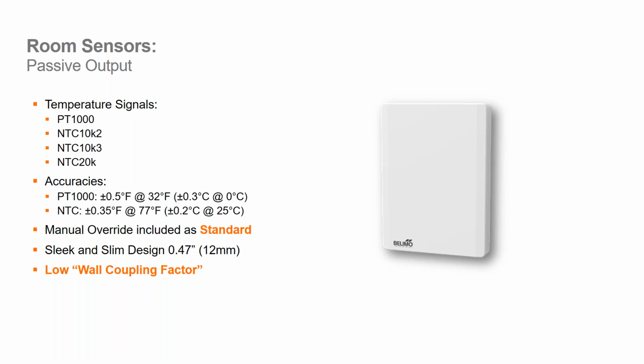The NTC models are plus or minus 0.35 degrees Fahrenheit. Again, manual override is standard, and it's not really visible. So if you look at this image here, you don't see the override. It's actually on the left-hand side, kind of hidden. So not everybody can just go in and override the VAV box or the fan coil unit. You've got to know where the override is.